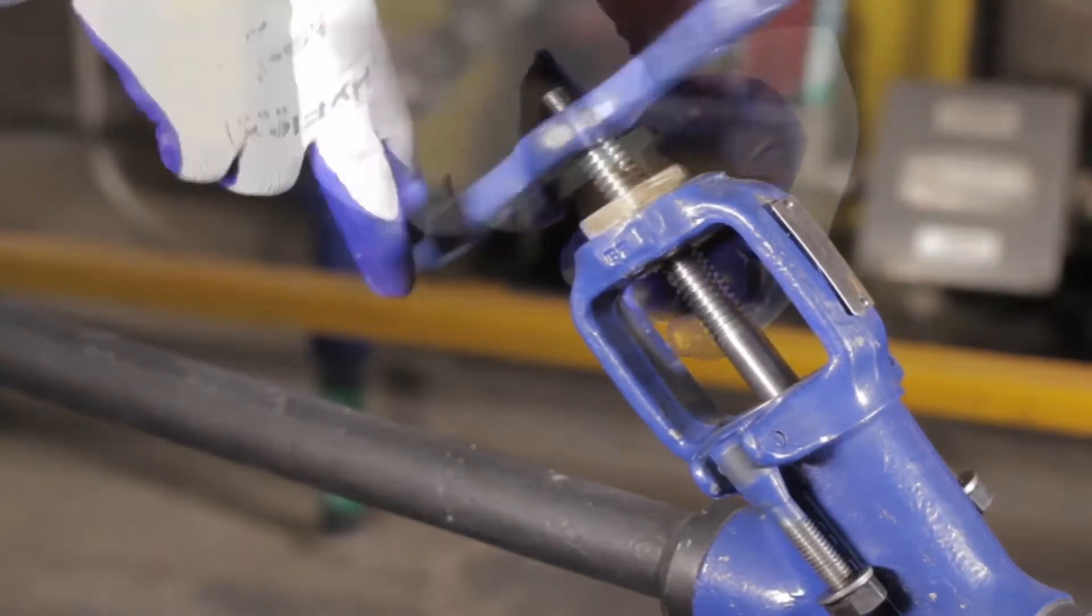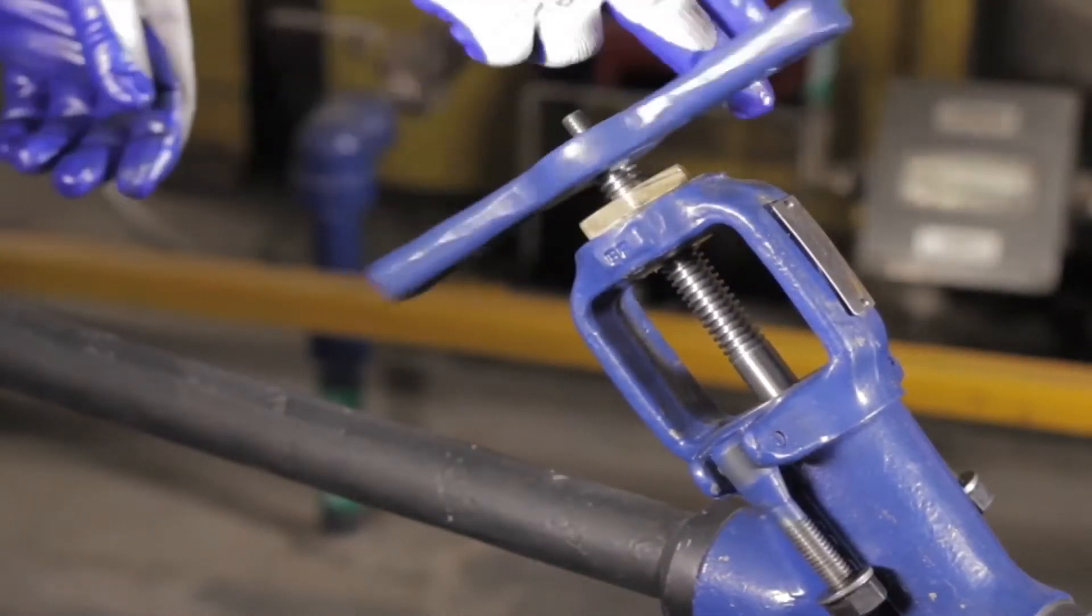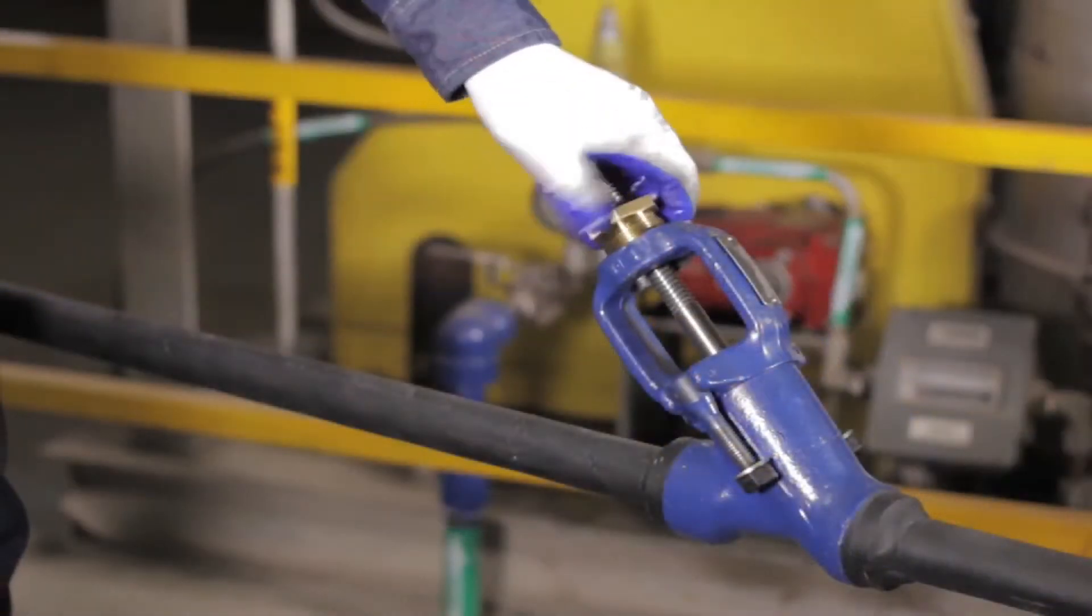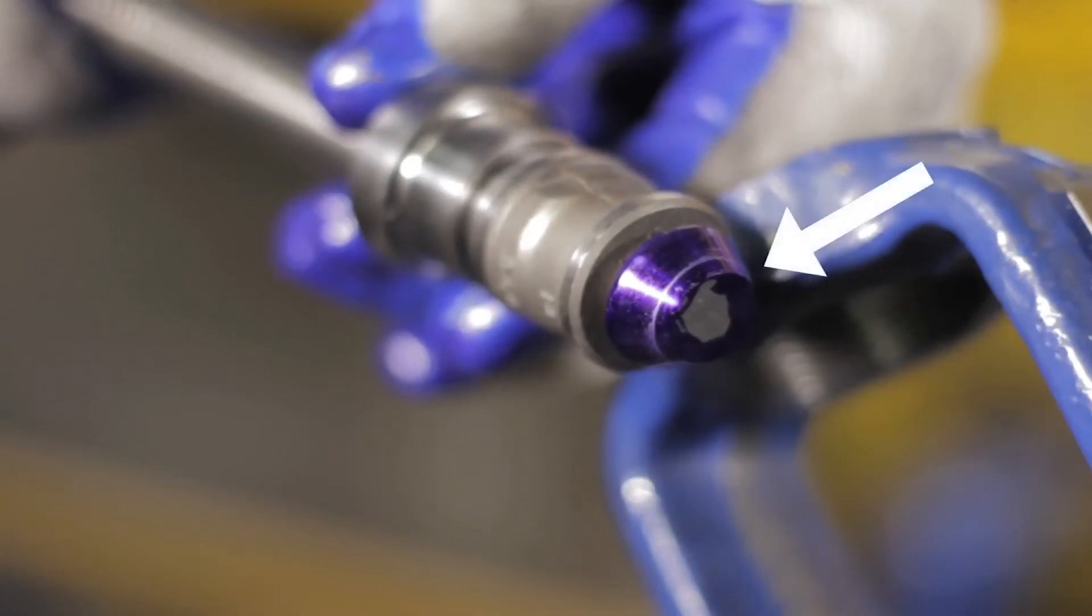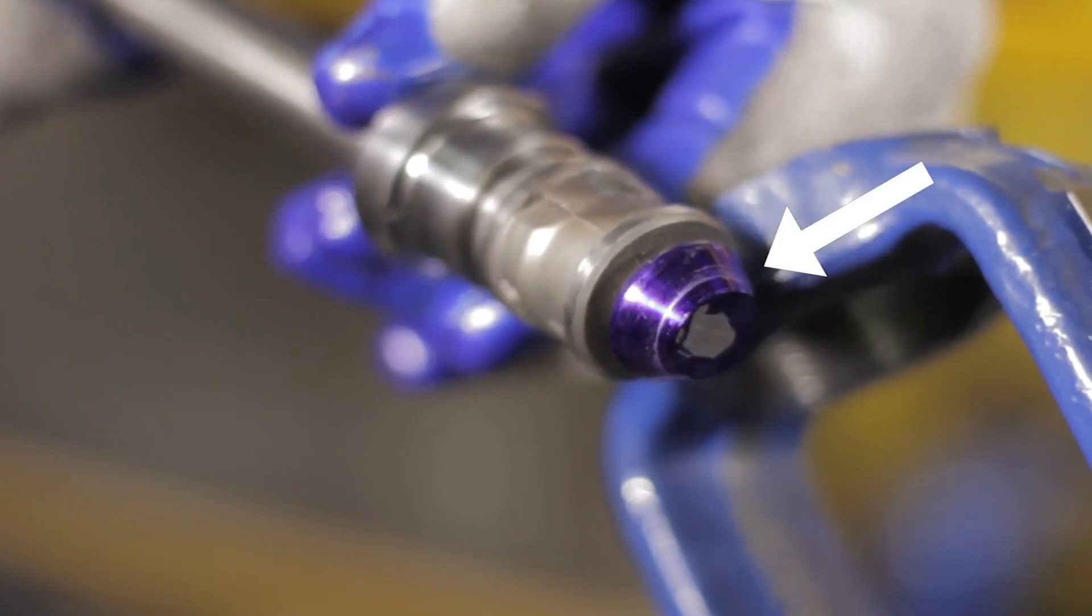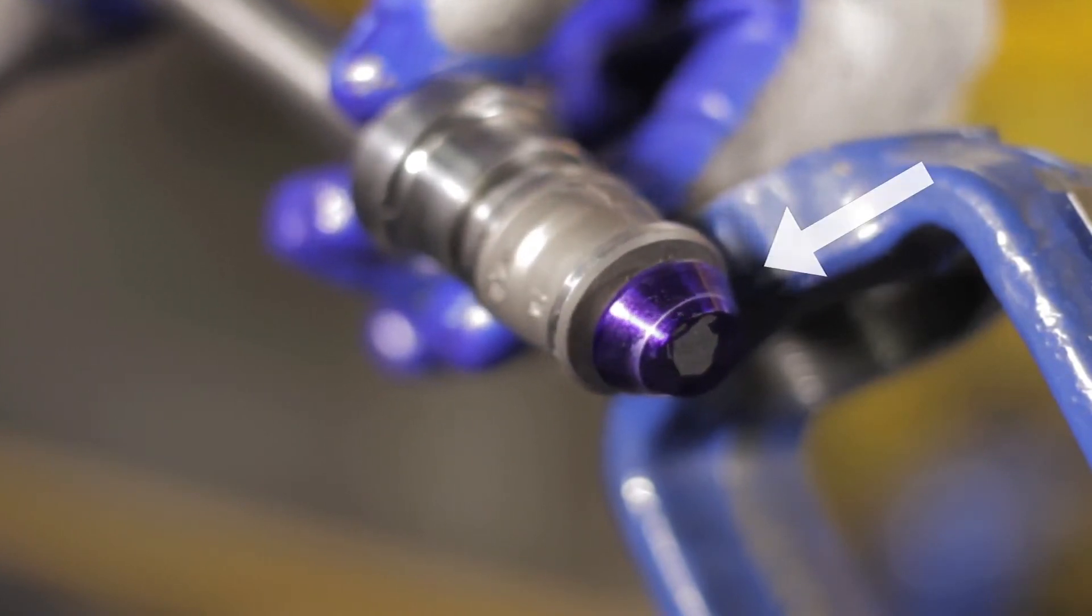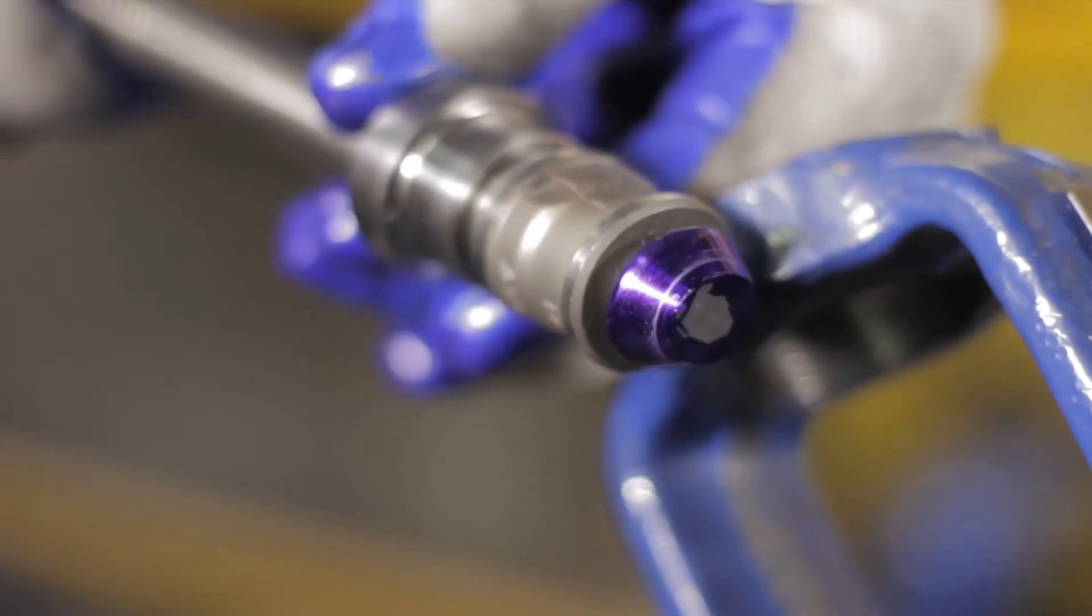Insert the stem disc assembly into the valve and screw in the yoke bushing for alignment. Close the valve tightly as if you were reassembling it. Then unscrew the stem and remove the yoke bushing. A continuous line will ridge around the face of the disc, showing that a perfect seating surface has been cut.